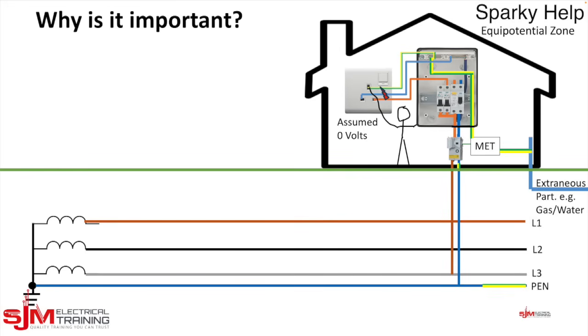But what happens if we get a fault? I'm not talking about a fault that potentially goes bang, although that would disconnect, or even a fault that took 5 seconds, as that fault would be there for 5 seconds. I'm talking about faults that might not have enough current to disconnect, for whatever reason. It might be a slightly faulty appliance, a slightly faulty installation, or whatever it happens to be. What can then happen is the CPC, the earth within that building, can go up in voltage.